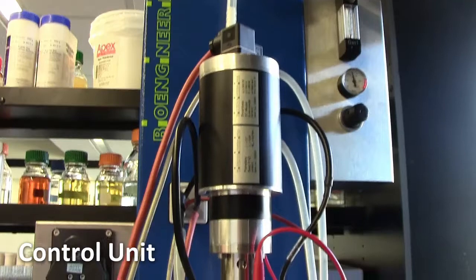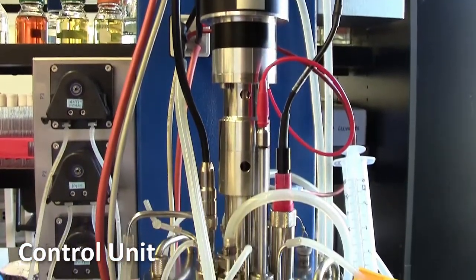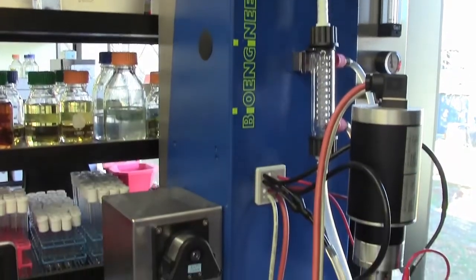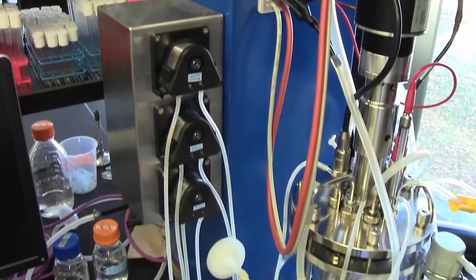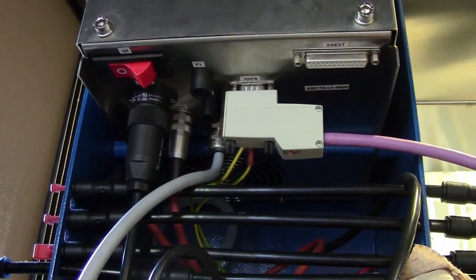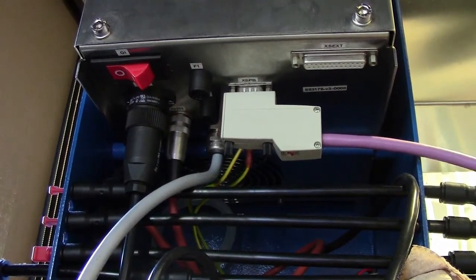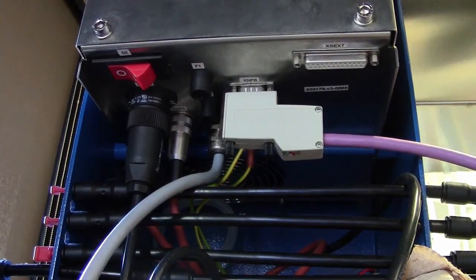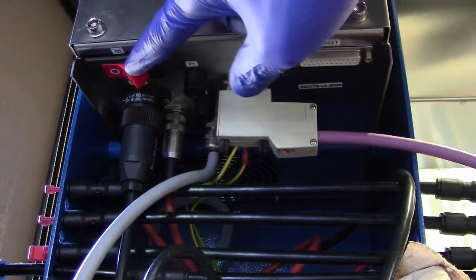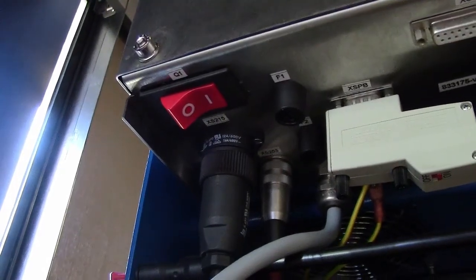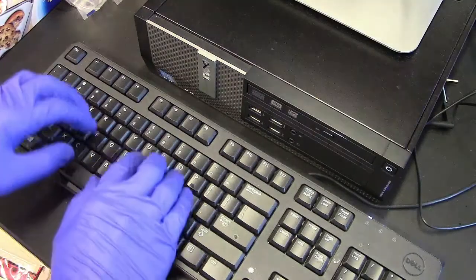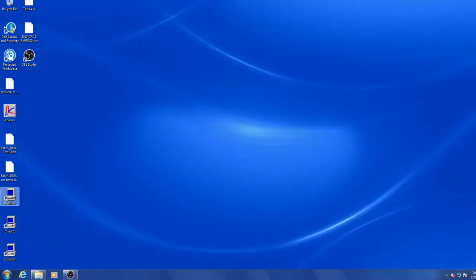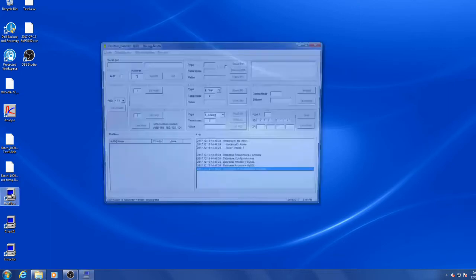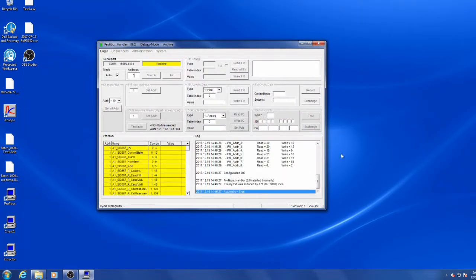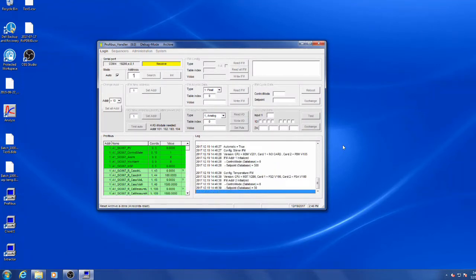The control unit. The control unit, or control tower, houses the electronics and mechanical components that allow the machine to operate. On the rear of the tower are connections for water, gas flow, and the computer or Profibus interface. And last but certainly not least, the main power switch is located on the rear of the machine as well. To start the machine in operation, first flip the power switch to on. Log on to the computer and start the Profibus application. This connects the computer to the machine and begins communicating with the various instruments. This runs in the background while the machine is in operation.